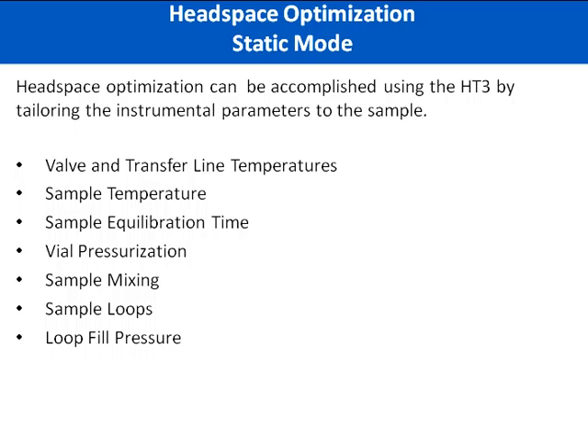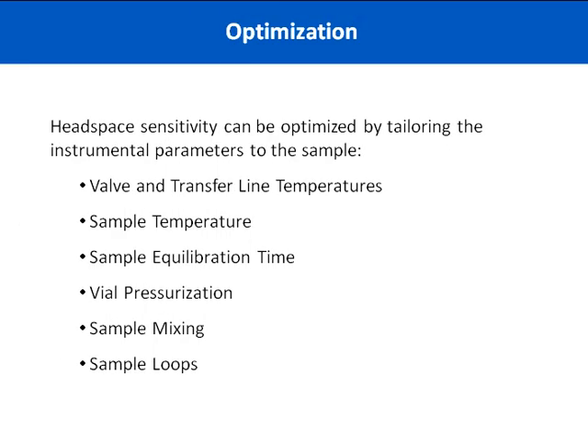Vial pressurization is going to assure that the sample completely fills the sample loop and keeps all samples and standards consistent in pressure — this is extremely important for reproducibility. Sample loops are available in different sizes according to your type of analysis. Currently we have a 100, a 250, and a 500 microliter sample loop, as well as larger loop sizes which can include 1, 2, 3, and 5 mil. The loop fill pressure is the pressure that the sample in the vial is going to decrease to in order to help fill that loop.